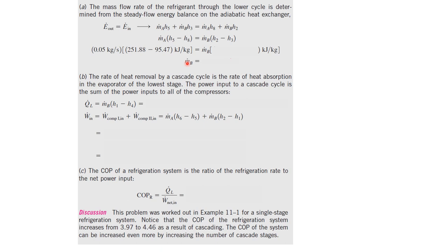Next, we want to find the rate of heat removal by a cascade cycle. This is nothing but the rate of heat absorption in the evaporator of the lower stage. At the lower stage you use H1 minus H4 times M.B, and that will give you the rate of heat removal from the evaporator. That should be straightforward.